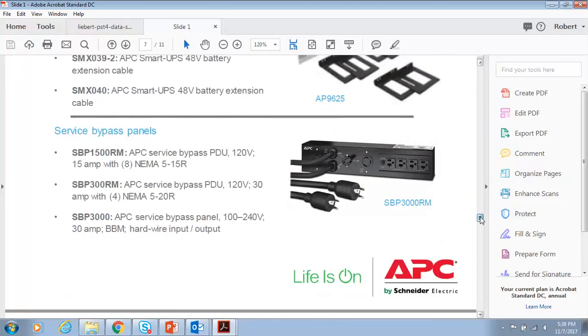Both Vertiv and APC offer something unique, a bypass module or maintenance bypass panel, so the UPS can get serviced while there's no interruption to the load. So if the utility is still up and the UPS needs some type of service, both APC and Vertiv offer this kind of wraparound maintenance bypass, which is really the outlets where your gear is plugged in. APC offers three different flavors here for their Smart-UPS, and you'll see Vertiv has a little bit more in their offering, but both are very similar.